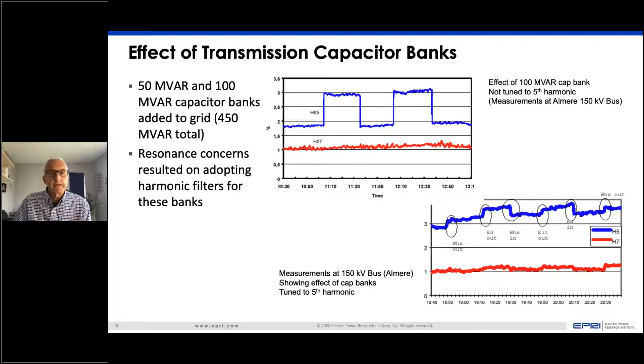Just one more example. This happens to be an example from Carolina Power and Light, which is now Duke Energy, converting a substation capacitor bank that was also causing fifth harmonic resonance on a circuit that had industrial loads that generated some fifth harmonic. You can see when it's switched in how effective it is at reducing the voltage distortion levels on that distribution system. So we learned a lot over the years of how to apply filters and how to avoid resonance conditions, but this really illustrates how compatibility is a coordinated issue between harmonics that are generated by nonlinear loads, and electric vehicle chargers are examples that we'll come back to, and the response of the power system in terms of creating resonance and solving those problems.